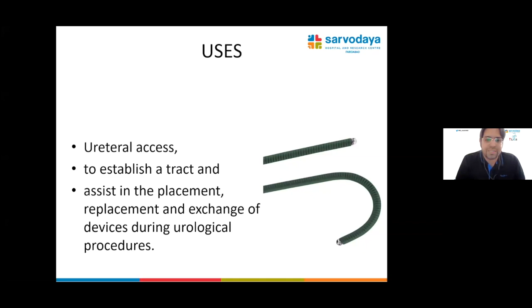For better access, the most important thing is the guide wire. They allow for ureteric access to establish a tract and to exchange devices during urological procedures. Most commonly used is the hydrophilic guide wire. It has a hydrophilic coating with an elastic nitinol core, available as 0.025 to 0.038 inch in diameter.